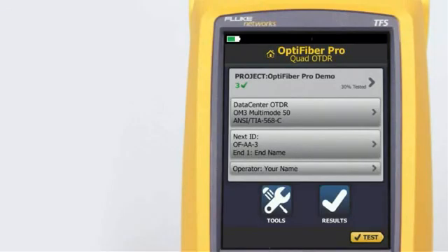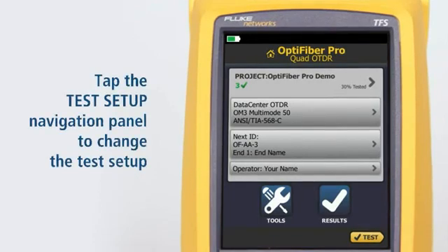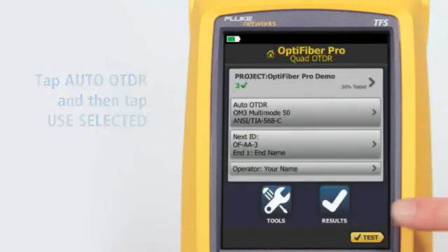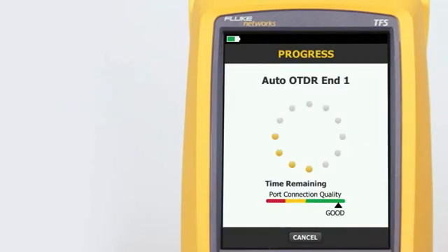The Auto OTDR test mode automatically selects settings that give you the best combination of test time, dynamic range, and resolution. It provides the best view of the events on the cabling, and is the easiest to use — the best choice for most applications. The previous test was run using the Data Center OTDR setting. Tap the Test Setup navigation panel to change it, then tap Auto OTDR and tap Use Selected. Now simply tap Test and the tester will determine the best settings to use for the fiber under test.